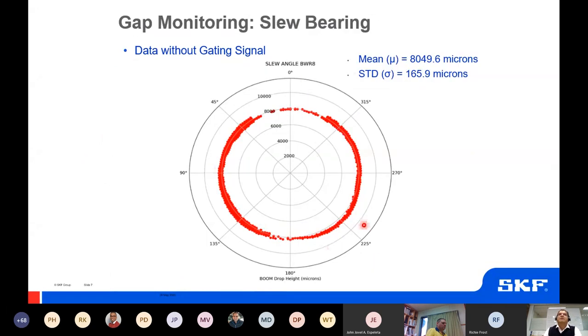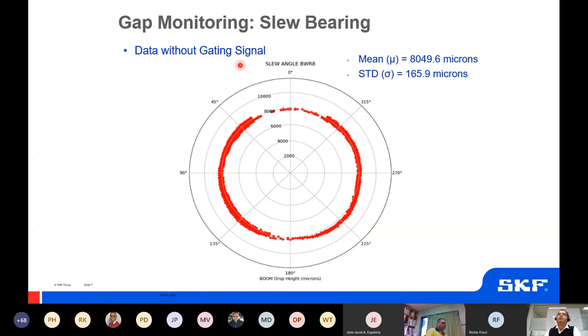When we map the same data onto a circular plot, we can see the smearing in the data at the micron level. The standard deviation in the data is 165.9 microns. While this is way better than the manual process, it is still not adequate. We can filter it further to collect data under the same conditions — data collected across the entire 360-degree circumference of the slew bearing under all operating conditions.